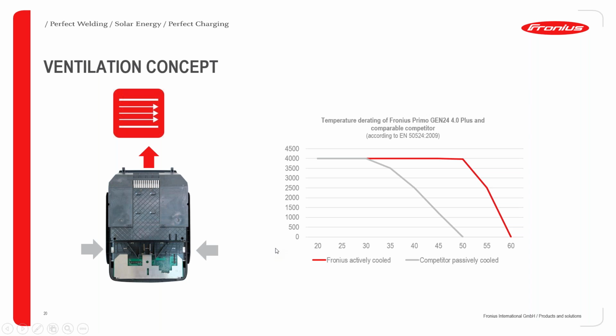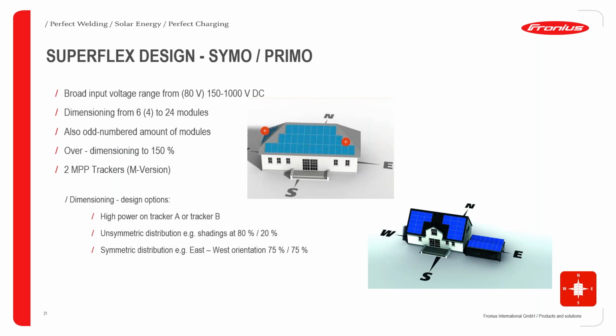And this coincides with a heat sink temperature of about 75 to 80 degrees Celsius. It is only when it gets to this stage that it begins to derate. So as you can see, it's a really rugged inverter that can, of course, withstand adverse temperature coefficient values. Good. So let's now talk about the Superflex design.